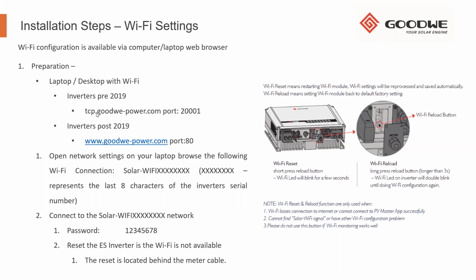Also, you'll notice here, we do have our ports available. On all of our newer inverters, you'll see this is the broadcast address and broadcast port. Sometimes on home networks and business networks, you'll get our Wi-Fi LED going to full blinking. Full blinking means we aren't communicating with the server. If there's a firewall in place or some sort of parental blockage on a home network, we always just need to make sure that we can open the ports for the inverter so that it can communicate outwards. Very often this can be an issue on sites where we go into full blinking, and we just need to double check that this is open for us to communicate.